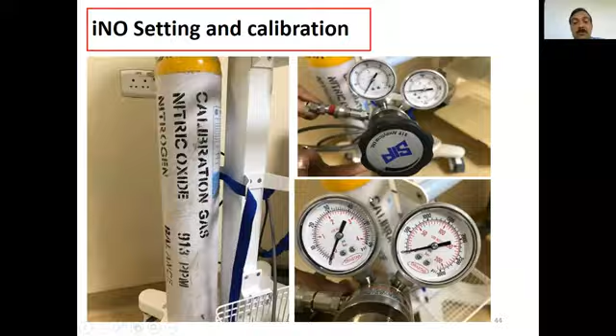Before we connect the nitric oxide, sometimes we need to calibrate the gas, and generally it is done by the service engineer or the biomedical engineer. This is a sensor which is present inside the nitric oxide unit. If you can see here, this is the nitric oxide sensor, and this is the nitrogen dioxide sensor. Based on the sensor, the display shows the nitric oxide that is delivered to the baby in the system. Each sensor costs about 40,000 rupees, and this has to be replaced every year. So the maintenance cost of this equipment is a little expensive compared to other maintenance systems, and it has to be calibrated regularly. I'm going to tell you how to calibrate this gas.